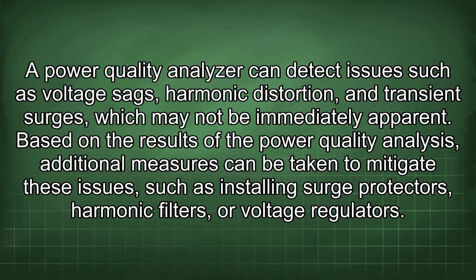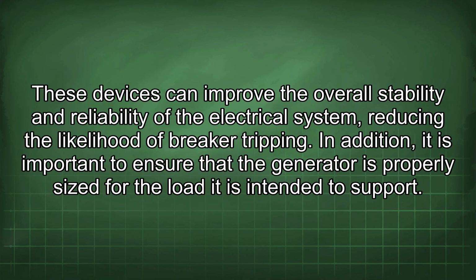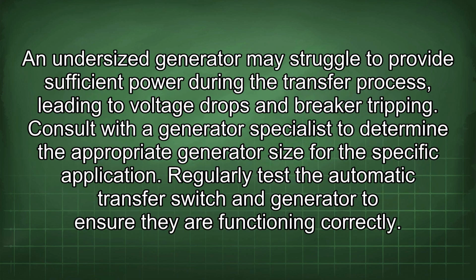Based on the results of the power quality analysis, additional measures can be taken to mitigate these issues, such as installing surge protectors, harmonic filters, or voltage regulators. These devices can improve the overall stability and reliability of the electrical system, reducing the likelihood of breaker tripping. In addition, it is important to ensure that the generator is properly sized for the load it is intended to support. An undersized generator may struggle to provide sufficient power during the transfer process, leading to voltage drops and breaker tripping. Consult with a generator specialist to determine the appropriate generator size for the specific application.